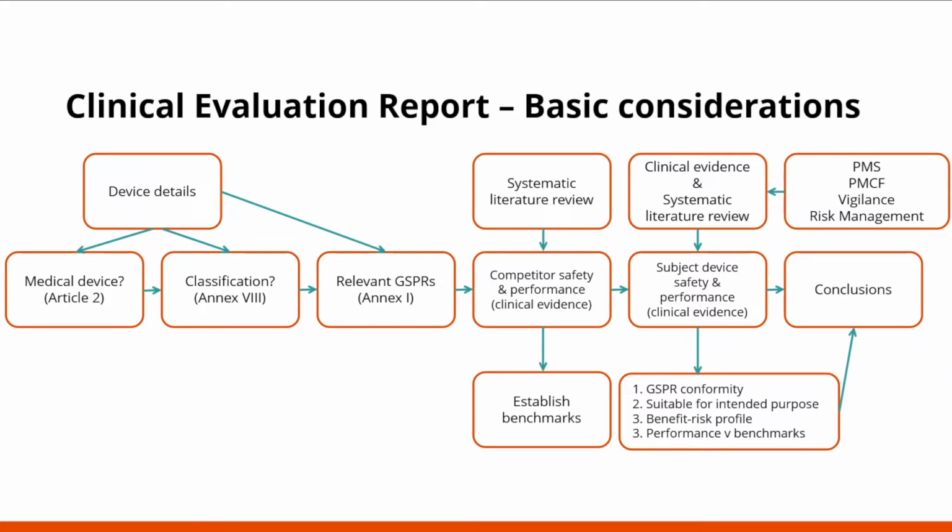So it really does pull information from the broadest possible range of sources, but by completing a clinical evaluation report in a structured way, it's possible to ensure complete alignment with the MDR, and assuming that the data is favourable, it's possible to conclude that the device is suitable for ongoing approval under the MDR.